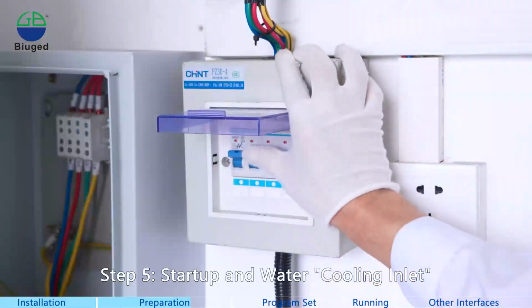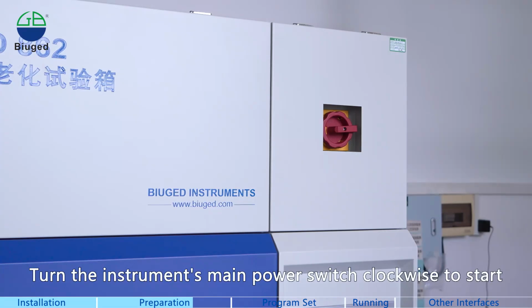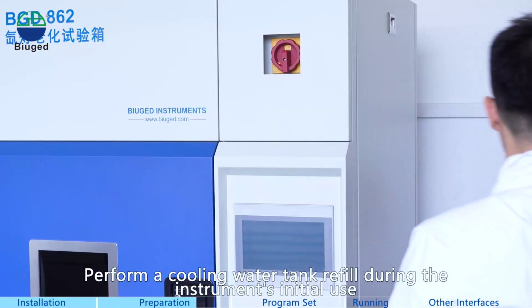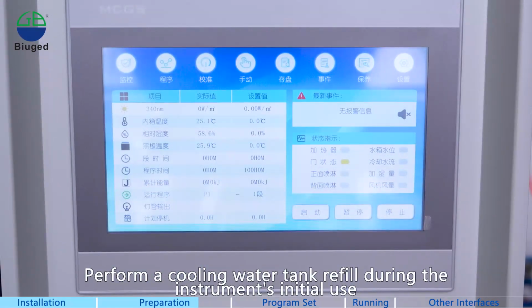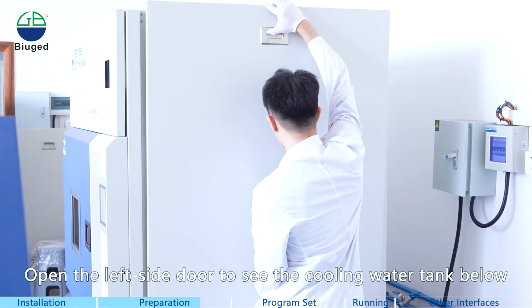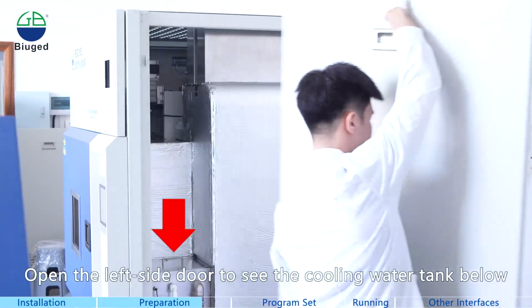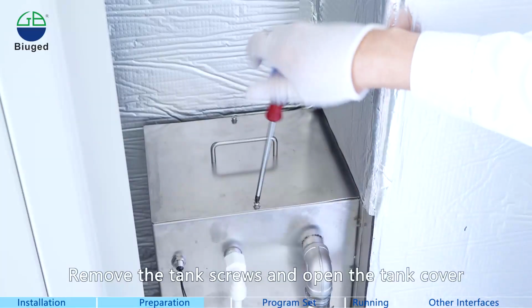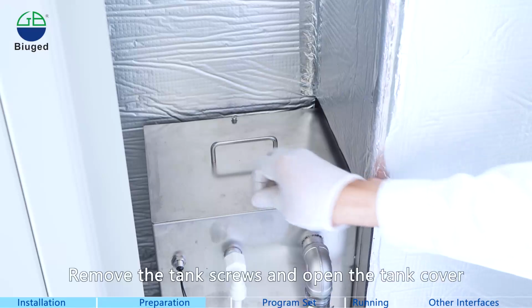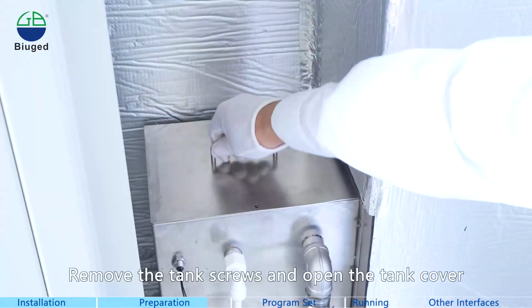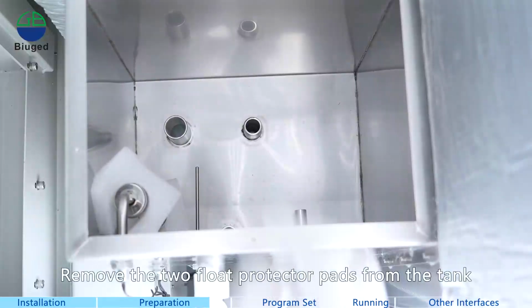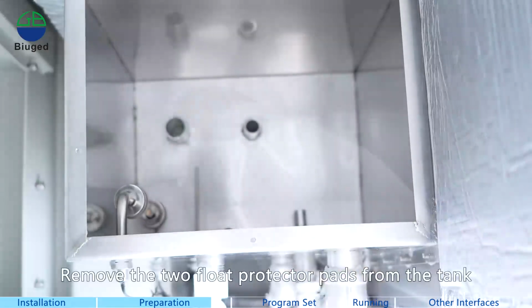Step 5. Startup and water tank refill. Turn the instrument's main power switch clockwise to start. Perform a cooling water tank refill during the instrument's initial use. Open the left side door to see the cooling water tank below. Remove the tank screws and open the tank cover. Remove the 2 float protector pads from the tank.